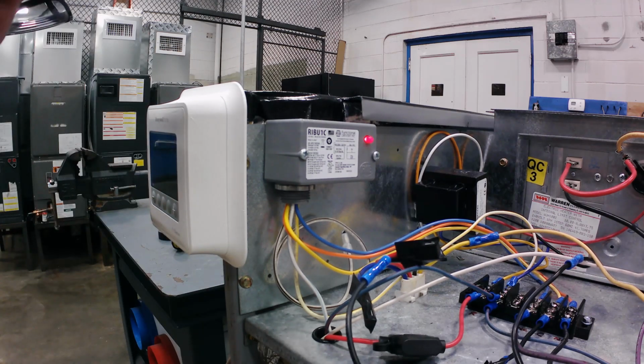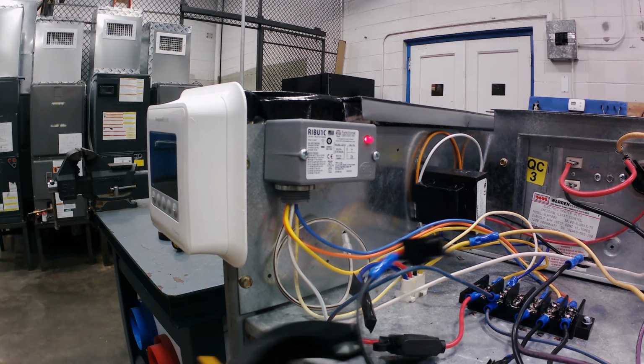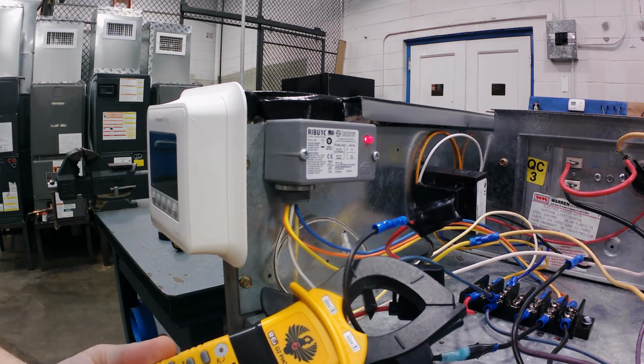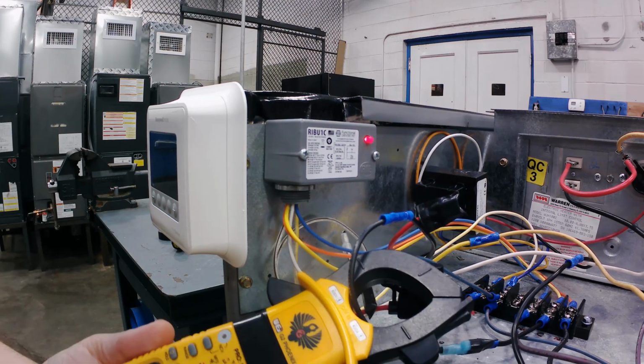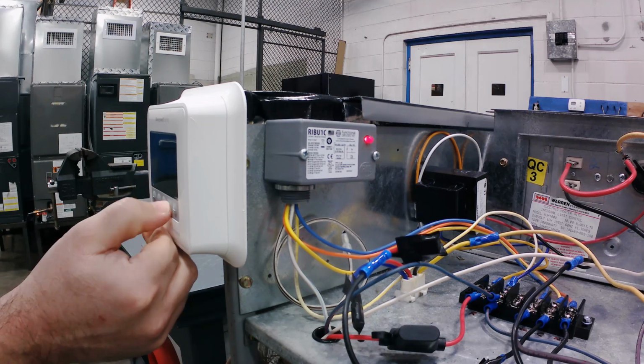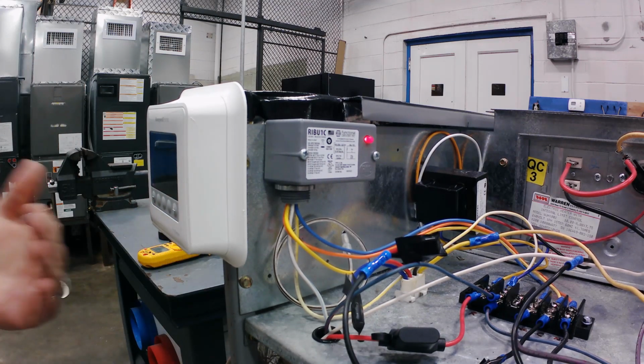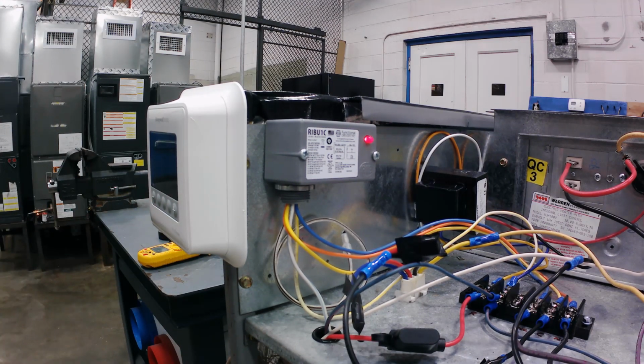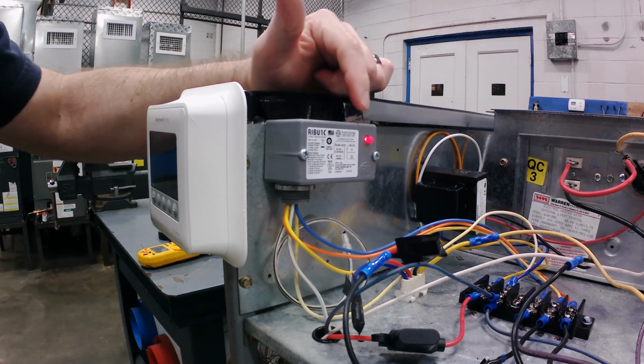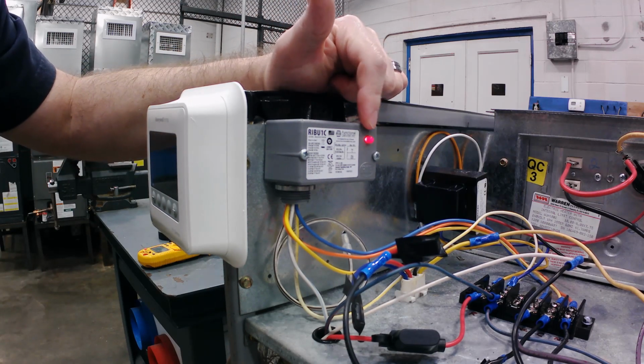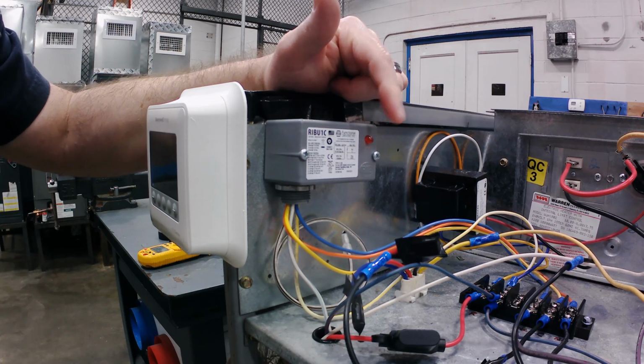And we can sit here and do our amperage checks if you wanted. And it's pulling about 1.2 amps. As soon as you turn the fan back to the auto position, then that red light's going to go away. So the red light is basically an indicator for whenever the coil has voltage applied to it.